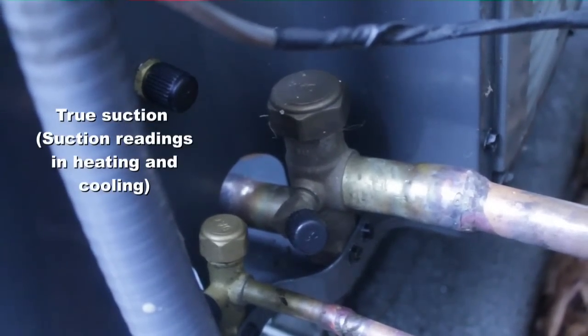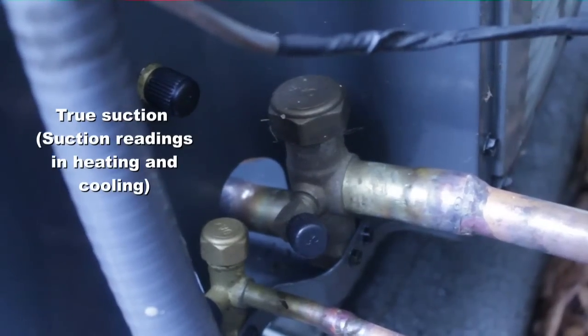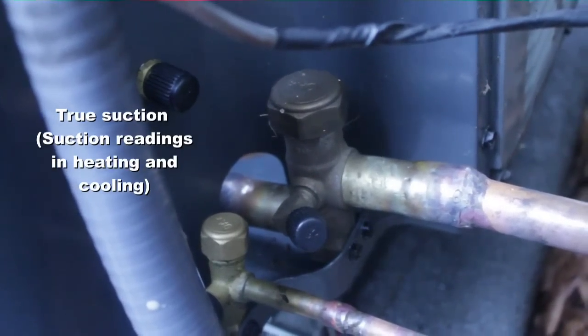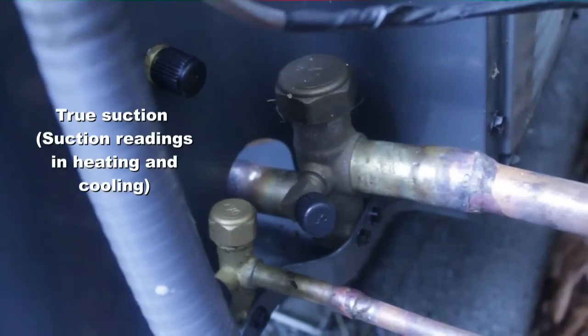If you look at the top left, you see a port by itself without a service valve. That is the true suction, no matter if you're in cooling or heating. This will give you a suction pressure near the compressor. In heating, this port can be used to charge.